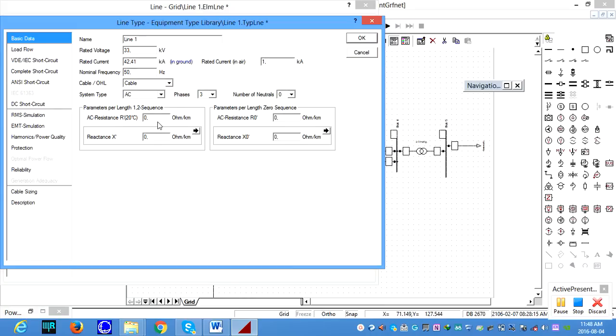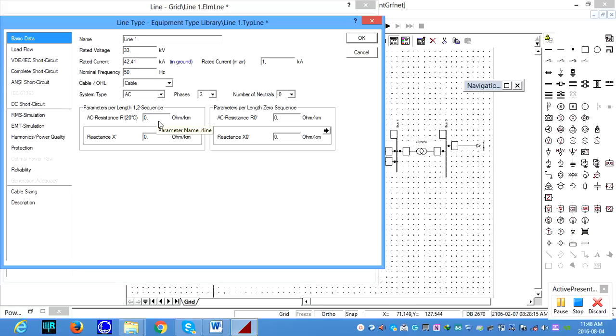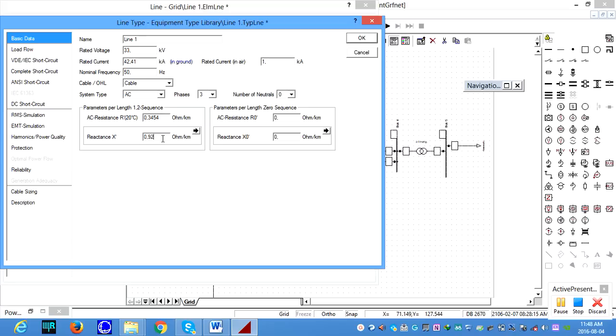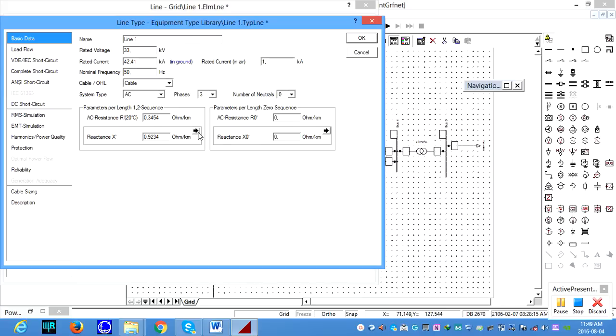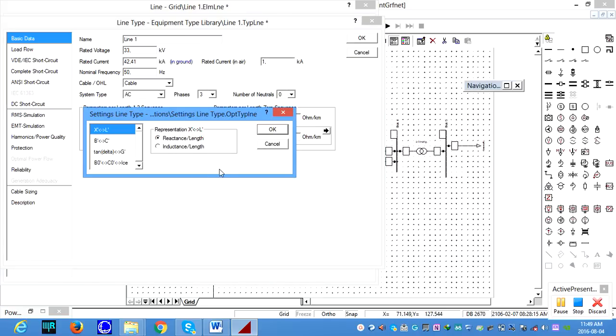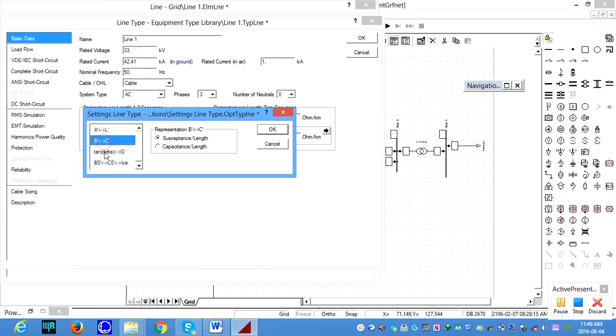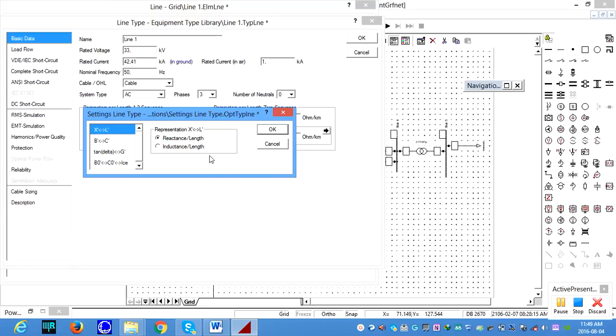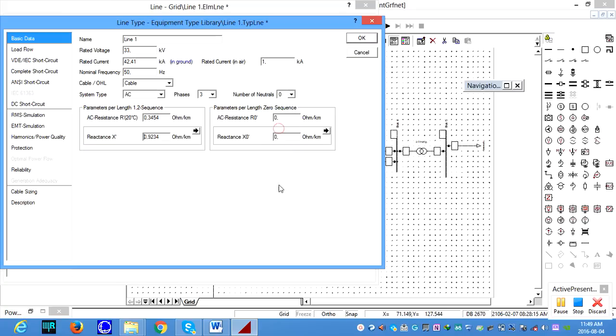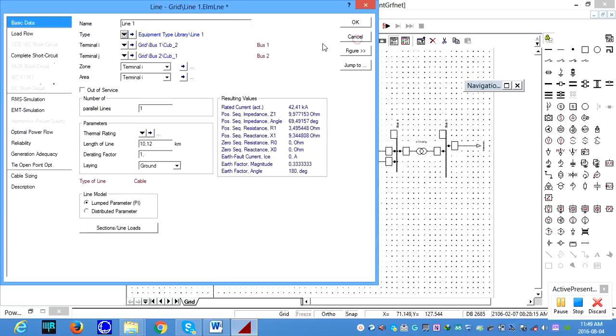And we also want to specify the resistance. The resistance supposed to be 0.3454, and the reactance 0.9234. This is a line impedance parameters. But in some cases, if there's options, you can change the parameter type. Either you can, instead of reactance, you can give an inductance, or you can give a susceptance according to the data that is given. In this case, we just keep it as reactance per length as per the data given. Okay, we are happy with line 1.